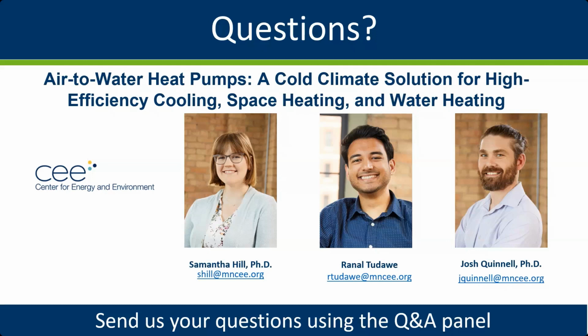Great question, Lauren. So I want to reiterate that air-to-water heat pumps are air source heat pumps, so we expect similar performance between the two different technology types. The main factor in determining what sort of system is the best fit for any application really lies on what kind of distribution system is planned and is the best fit for the building. So if the building already has hydronic distribution, air-to-water heat pumps are great to consider. And if the building does not have hydronic distribution, it's likely far more cost effective to use an air-to-air heat pump instead of an air-to-water heat pump.